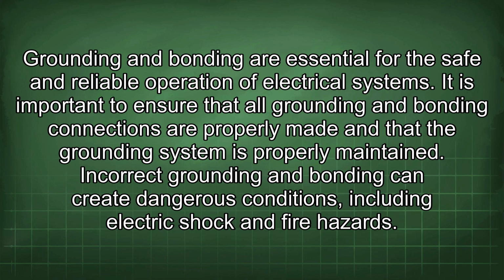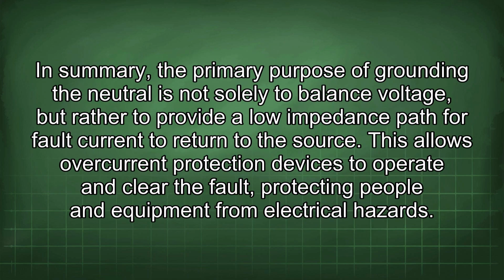Grounding and bonding are essential for the safe and reliable operation of electrical systems. It is important to ensure that all grounding and bonding connections are properly made and that the grounding system is properly maintained. Incorrect grounding and bonding can create dangerous conditions, including electric shock and fire hazards. In summary, the primary purpose of grounding the neutral is not solely to balance voltage, but rather to provide a low impedance path for fault current to return to the source. This allows overcurrent protection devices to operate and clear the fault, protecting people and equipment from electrical hazards.